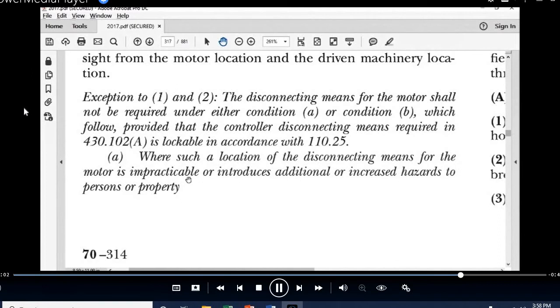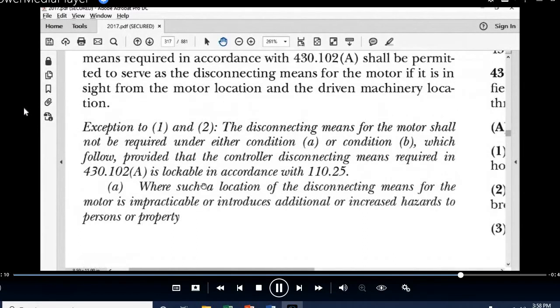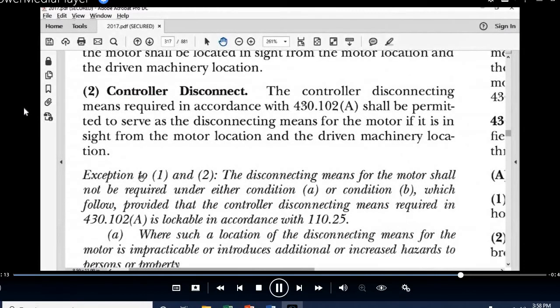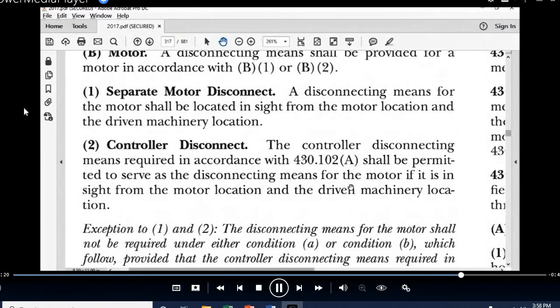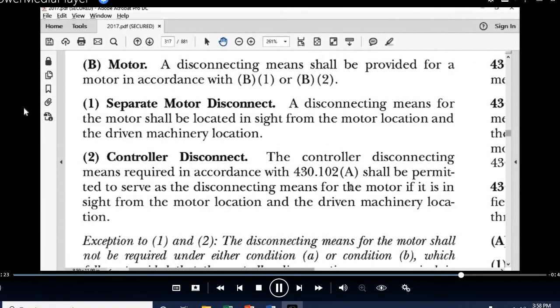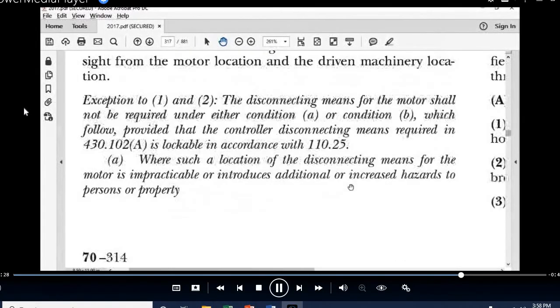Such a disconnect is not required if it's impractical. Yeah, that's not practical. Like, what do you mean if it's impractical? Can you scroll up just a little? This isn't the controller disconnect? Well, this is an exception to 1 and 2, and it's dealing with the motor disconnecting means. You can use a controller disconnect for the motor, but you still have to have a disconnect within sight of the controller, back on A. Right. Now, a disconnect is not required within sight of the motor if it's impractical. Can you think of any examples where it would be impractical to have a disconnect within sight of the motor? Eric? Pond pump.